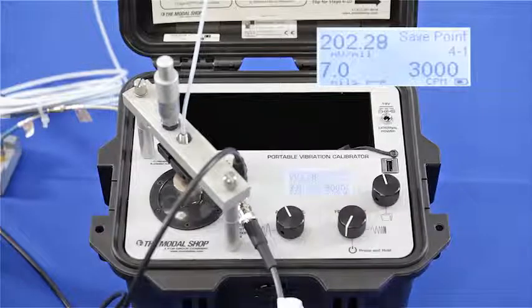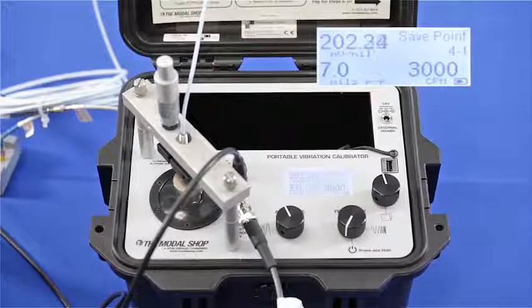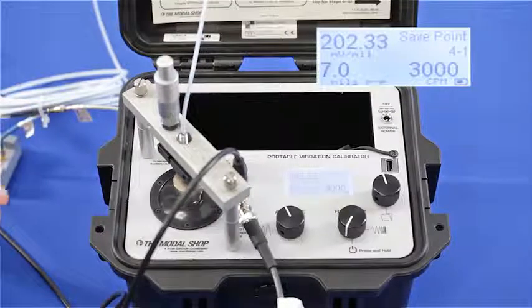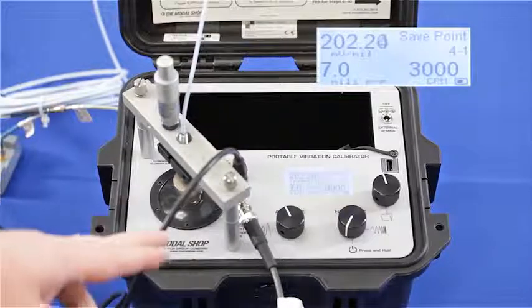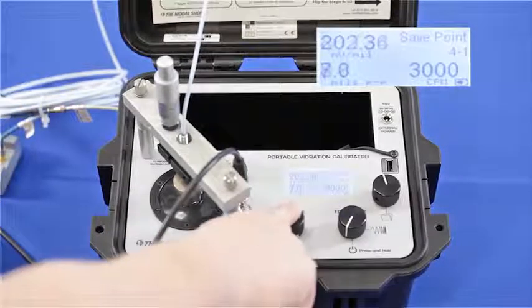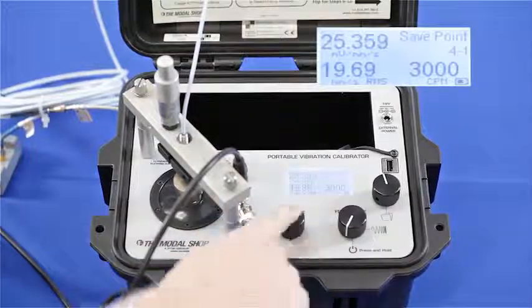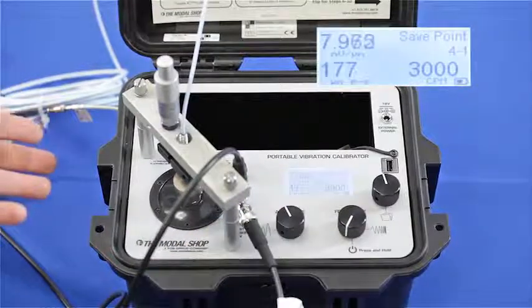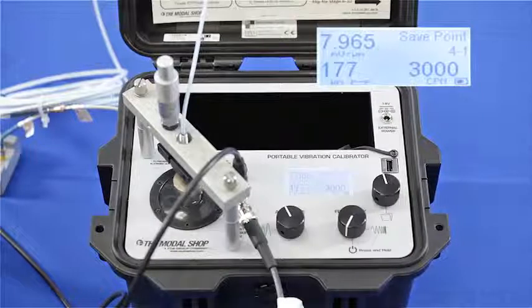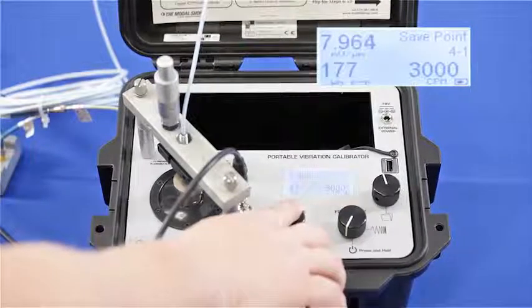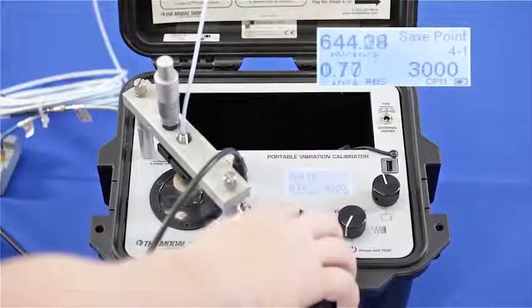My initial gap voltage is correct, and here on the screen you can see that I'm calibrating my proximity probe with 5 meters of cable in my 5-meter system at 7 mils peak to peak and 3,000 cycles per minute, and my output is 202 millivolts per mil, or in microns, the output is 7.96 millivolts per micron. Both of those values are well within tolerance for this 200 millivolt per mil system.